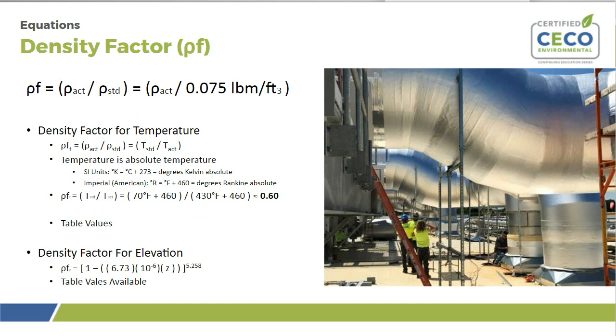To have a correct correlation between velocity and velocity pressure, a density factor is used to correct for temperature and elevation other than standard. The standard for air at 70 degrees and sea level is 0.075 pounds per feet cubed. Actual temperature is typically measured in degrees Fahrenheit or degrees Celsius, and in order to determine the density factor, the absolute temperature must be utilized. And degrees Fahrenheit would be converted to degrees Rankine, and degrees Celsius would be converted to degrees Kelvin. There are equations that provide this correction, as well as tables for both the elevation and temperature density factors.